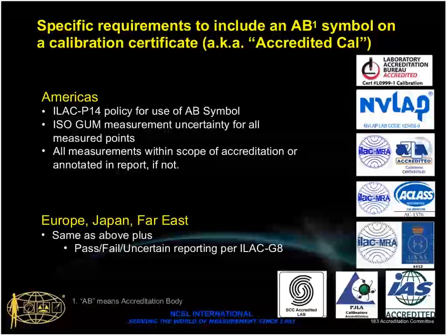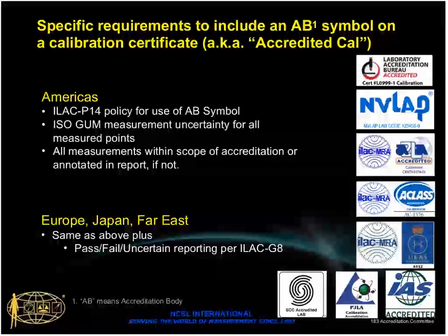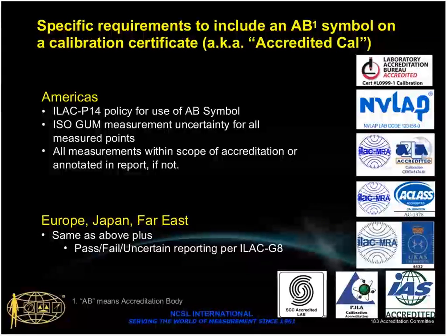P14 from ILAC has a policy about the use of the symbol. If you think about the fact that you could have some accredited work and some non-accredited work, most accreditation bodies allow both to be reported on the same certificate, provided the majority is accredited, and providing that there is no misleading intent or effect. And so it's a matter of whether, when you view that certificate, overall it is an accredited job. So the rules for that are in the ILAC document P14. You should be able to rely on the fact that the laboratory complies with it if they're accredited.